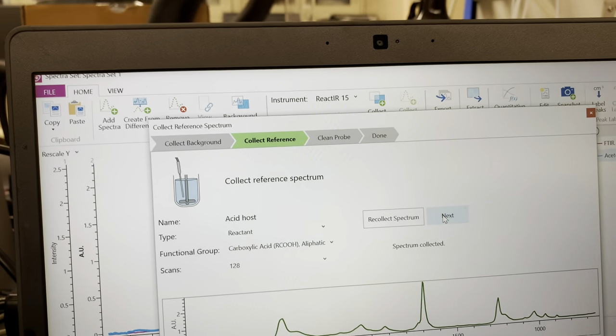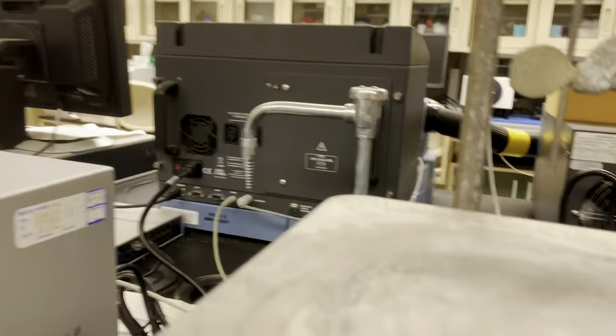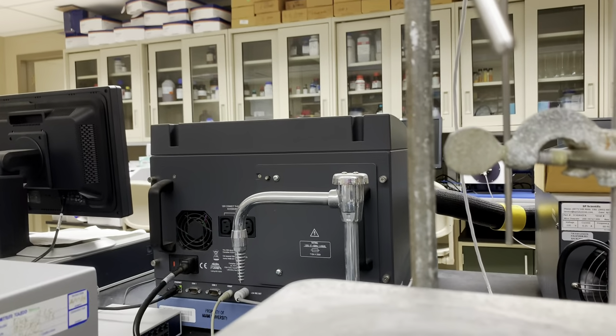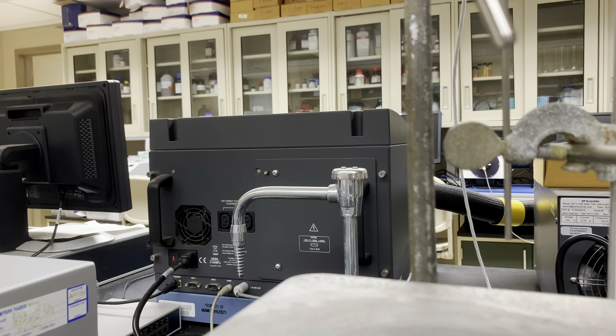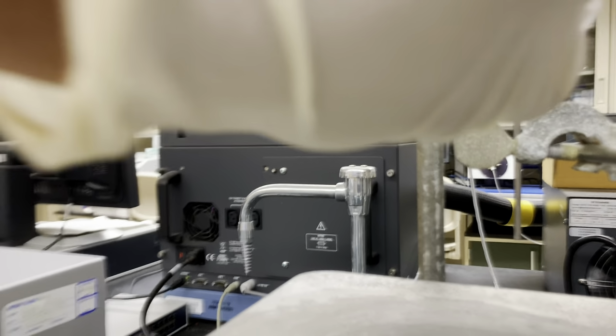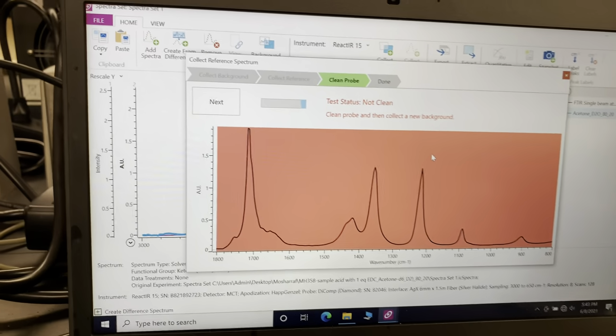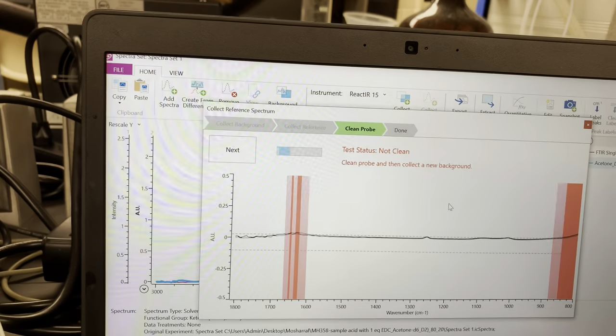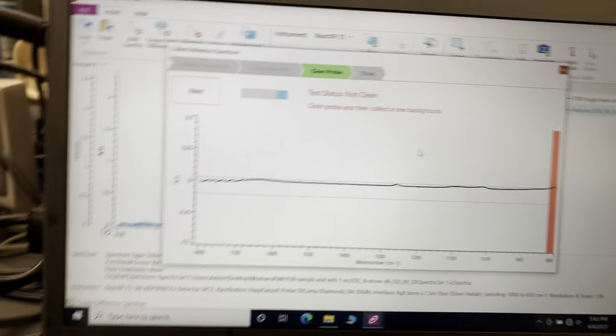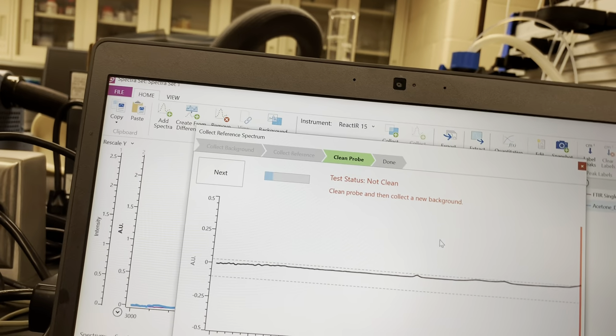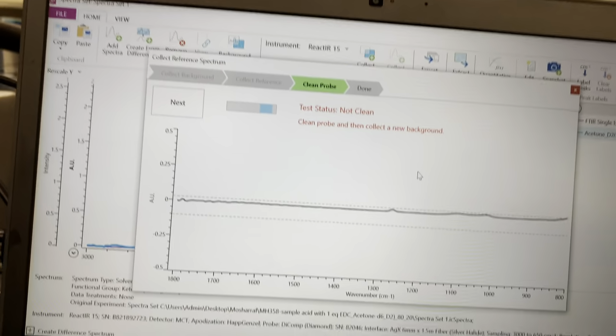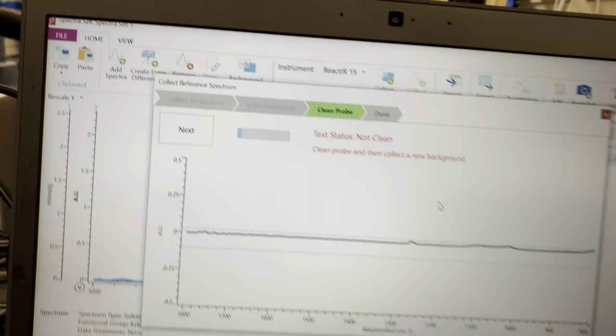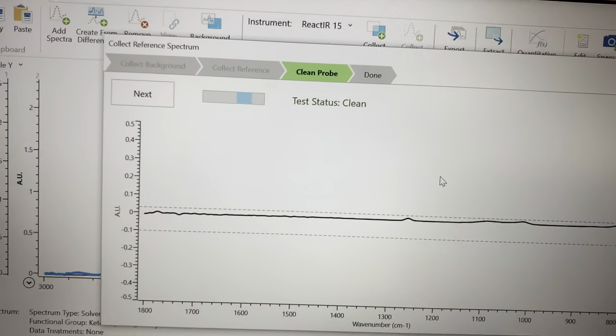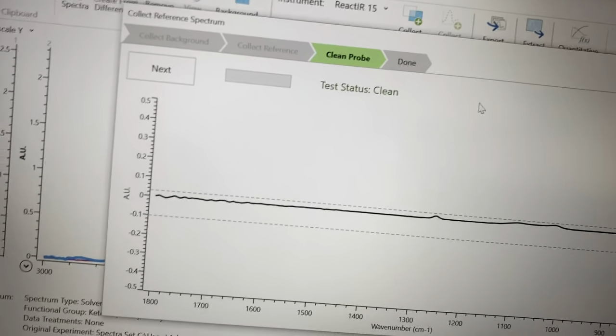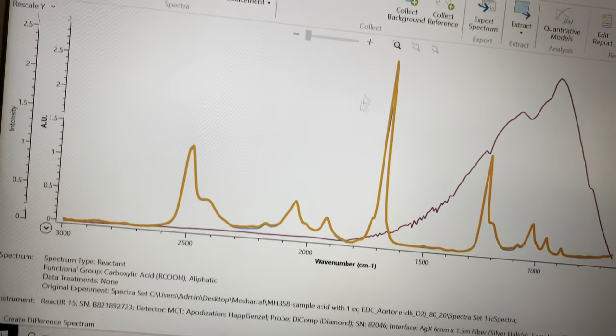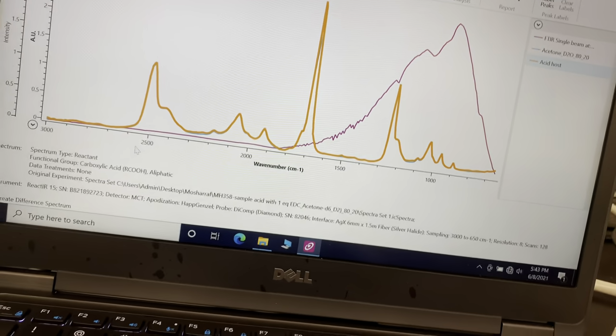Now click next and you'll see a prompt to wipe the probe tip with a dry Chemwipe. Once it is done, the red indicator will be gone. It is still showing that there might be some solvent not cleaned, the probe test status is not clean, so clean the probe and then collect a new background. Here you see that the baseline is a straight line, and now the test status is clean. Click next. Your reference collection is done.